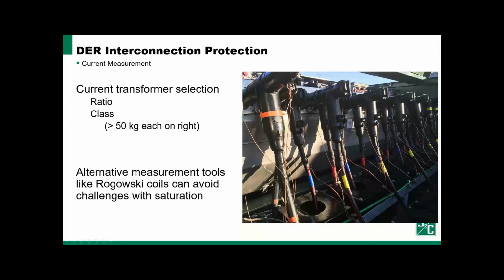Over on the right, you can see current transformers, which are shown right here, selected to work for a microgrid application. This can result in having quite physically large current transformers, because we need a high class and a large amount of iron to avoid saturation with the low ratios we need to detect the current. These current transformers you see in the image are quite large. In fact, the current transformer for each phase in this switchgear weighed over 50 kilograms. So these were physically quite large current transformers.